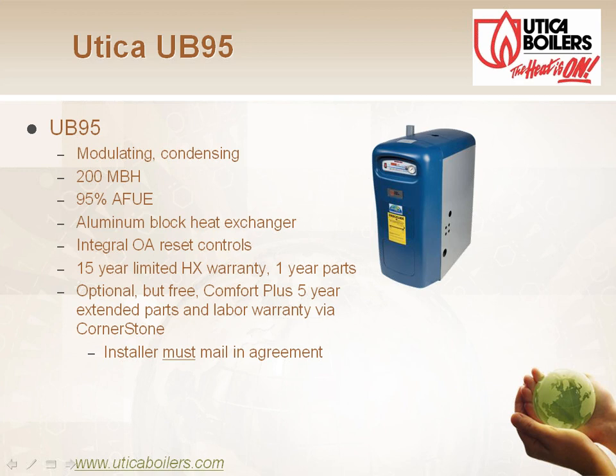And then the last line I want to show you here is Utica. Utica is a boiler manufacturer we've been dealing with for several years here, and the highest efficiency boiler that they have on their line today, and that's going to change in a couple months here, but right now it's the Utica UB95, which is 95% AFUE. It's modulating condensing just like the other boilers. He has an aluminum heat exchanger instead of stainless steel. Built-in outside air reset controls just like the other boilers. 15-year warranty on the heat exchanger, 1 year on the parts.